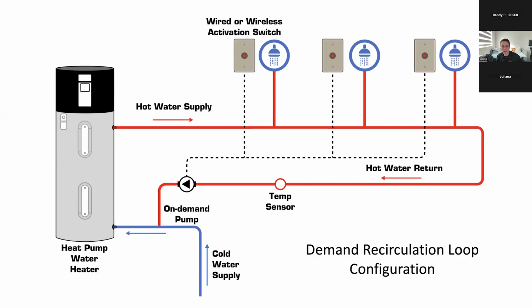So anyway, here we see a diagram of a recirculation loop where you have an on-demand pump on the return line, your temperature sensor, and then you have an activator at each fixture in the house that can be either an occupancy sensor or a manual switch. And so again, as long as the loop is satisfied, if I walk into a bathroom and walk in front of an occupancy sensor or push a button, the pump will not turn on because my temperature sensor says I'm satisfied. The pump does not need to run.